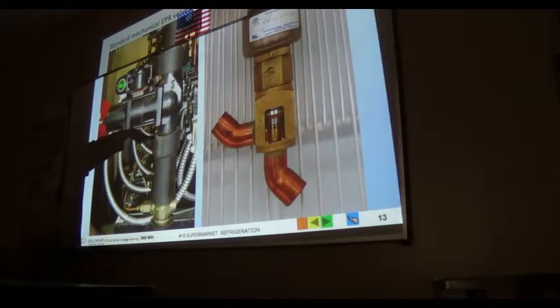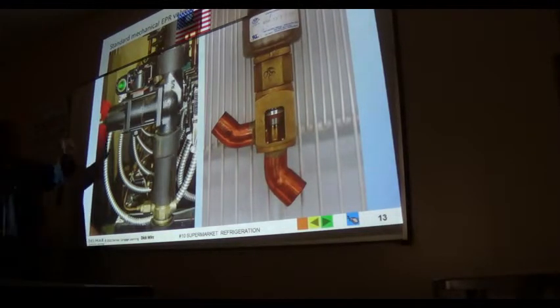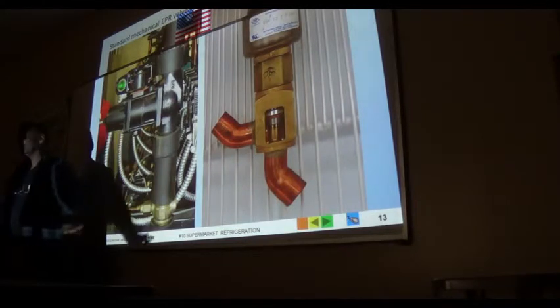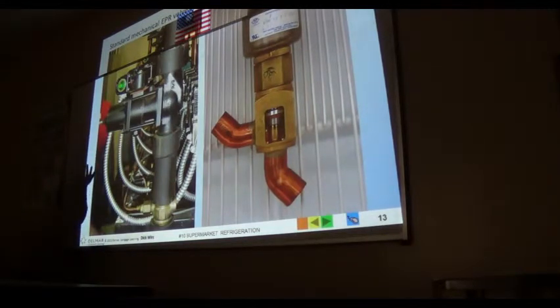It's going to say, you know what? Forget it, I ain't doing nothing. Stubborn valve. A system with that and a TXV always behaves as if it has an automatic expansion valve. Once that's present, the two systems mimic each other in performance. Like I said, it's not going to allow me to go into a hot pull-down. These systems are designed to more or less hold and maintain a temperature, not to come from above and pull it down.